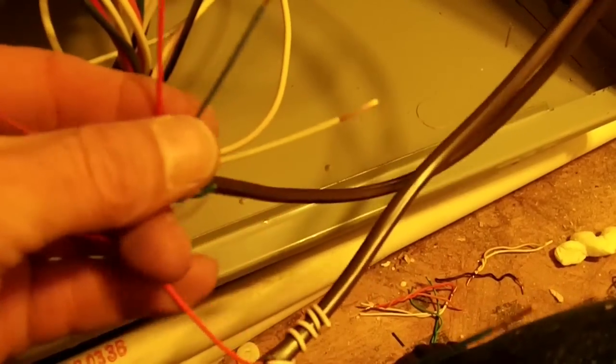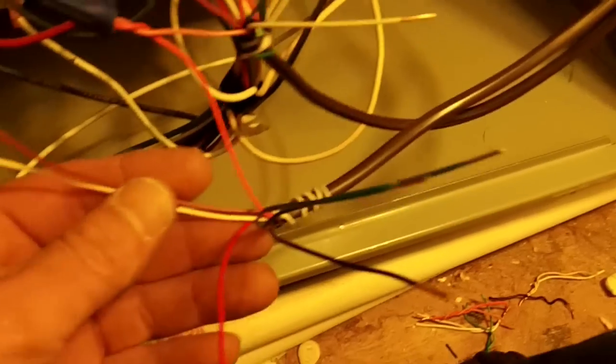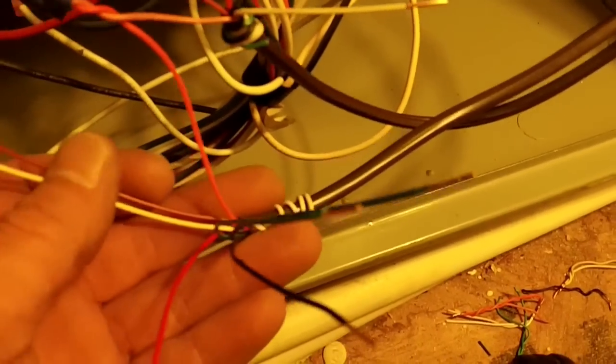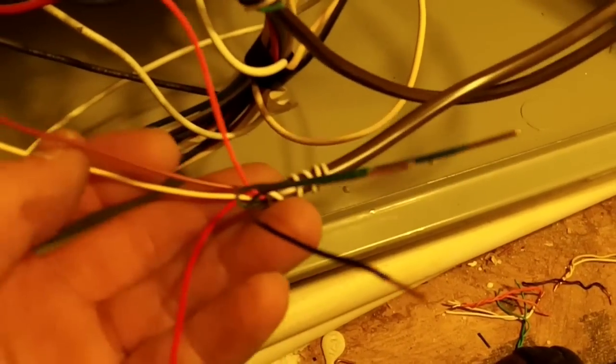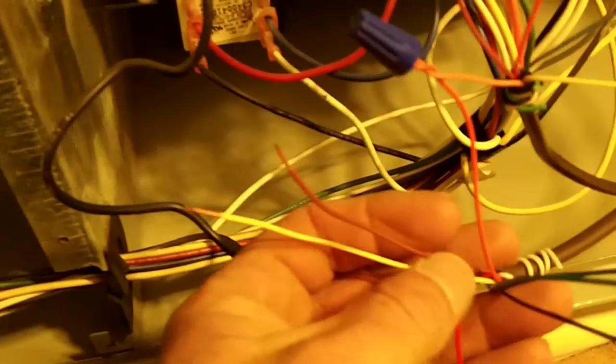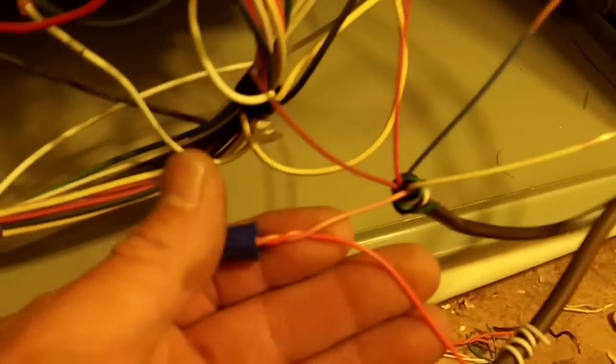Alright, so I've had to rewire the low voltage and fix it back the way I really want it to be done. Being a geothermal, we're not going to really need any backup heat at all, but since it's a gas furnace, we're going to need some sort of emergency heat. It gets wired up pretty much the same way—you got your orange wire going to your reversing valve, your 24-volt hot, and then your common, which is the blue.